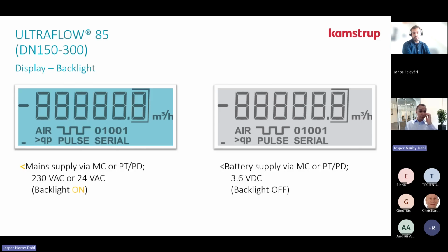Now, what can be shown on the display? The first thing: it's now possible to have a backlight on the display on the flow sensor. So the display can either be on or off, meaning when you order the ULTRAFLOW 85, you have to tell if you want the backlight on or off. We do not recommend having the backlight on if the calculator is battery supplied. It's important for me to say there is no battery inside the display of the flow sensor. The power comes directly from the calculator. So this is a backlight. It can either be on or off.